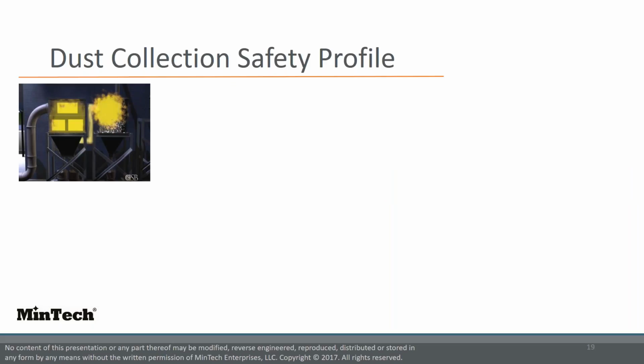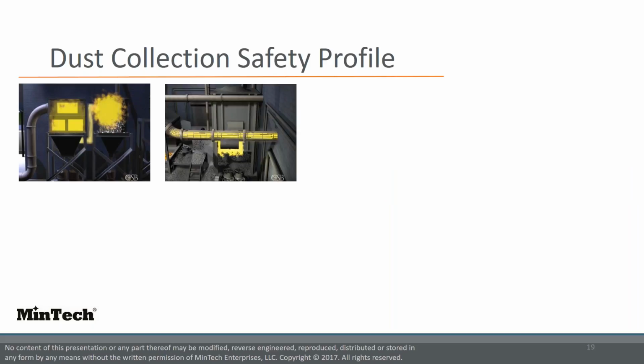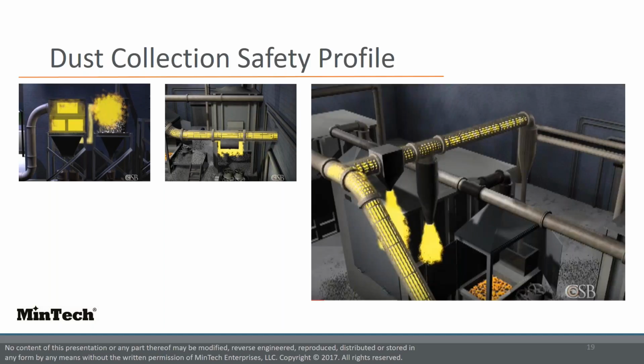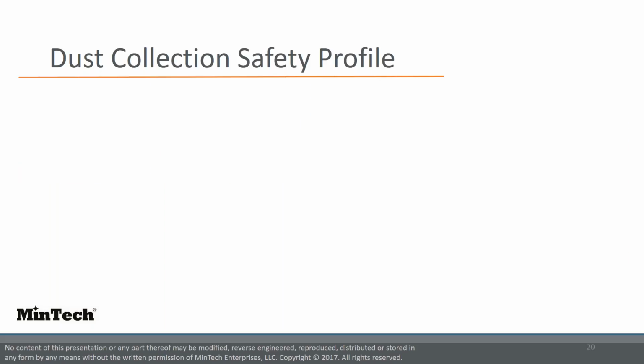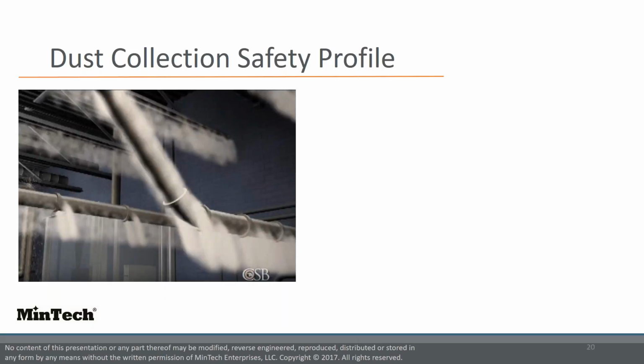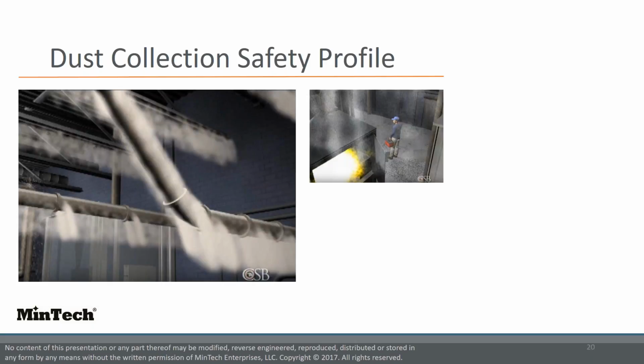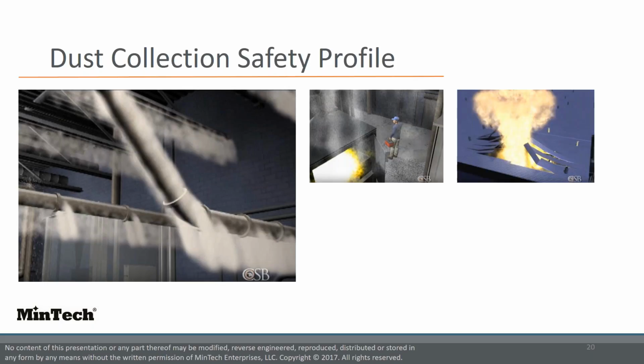A metal ember or an impact spark ignites dust inside the dust collector, causing an explosion that moves upstream to the drop box. The fireball and pressure wave continue upstream through the ductwork into the facility. As the fire spreads through the ductwork, it gains in intensity. Meanwhile, the initial explosion in the dust collector shook loose dust that had accumulated inside the plant. That falling dust meets with the fire traveling through the ductwork and triggers a second and much larger explosion. The secondary explosion is usually the one that causes the most property damage and human casualties.